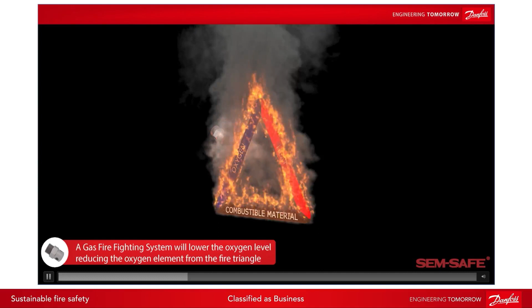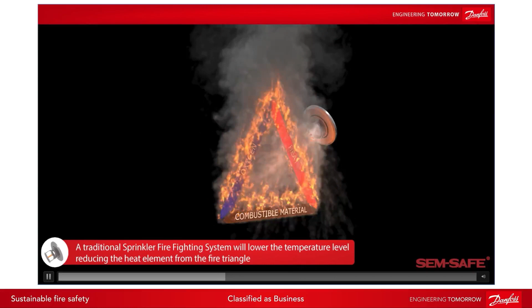It's just a combustion triangle to understand why high pressure water mist is using less water than a sprinkler system. Because, for instance, I think it will start with the gas. The gas extinguishing system is taken away. If you take one piece out of this triangle, the fire is put out. Gas extinguishing system is taking out the oxygen. The sprinkler system is taking away the heat, and the high pressure water mist is taking away both. And this is the main reason why we use much less water to result in the same or even better performance than a conventional sprinkler system.